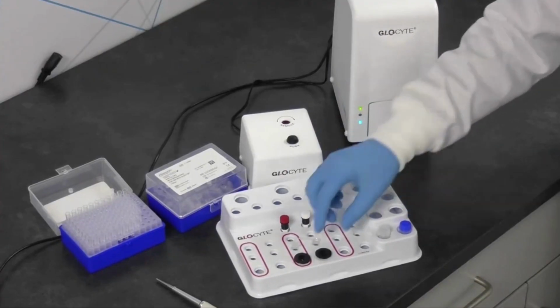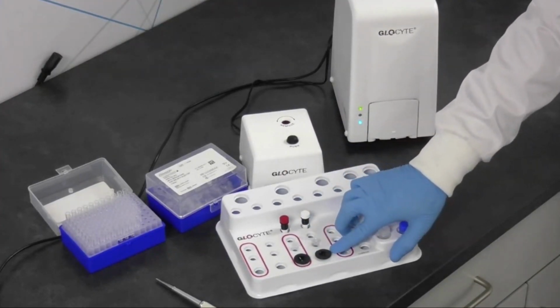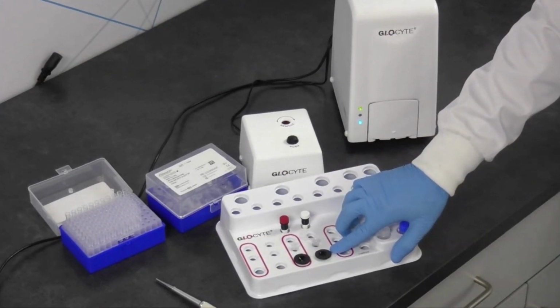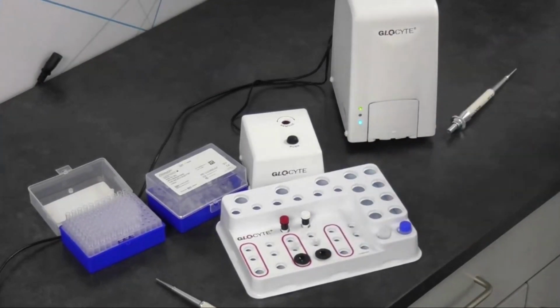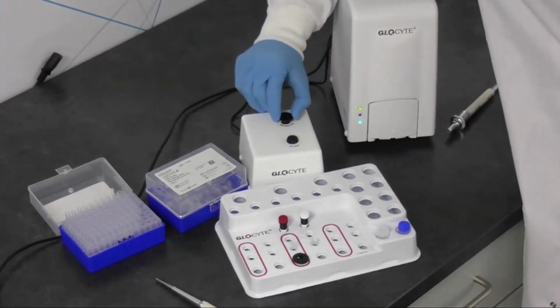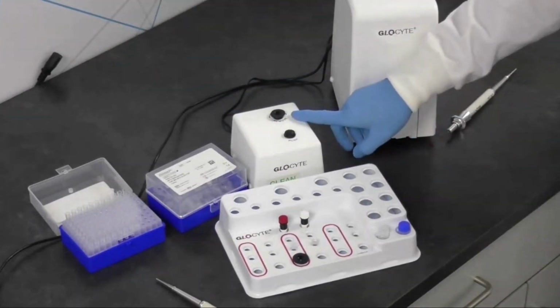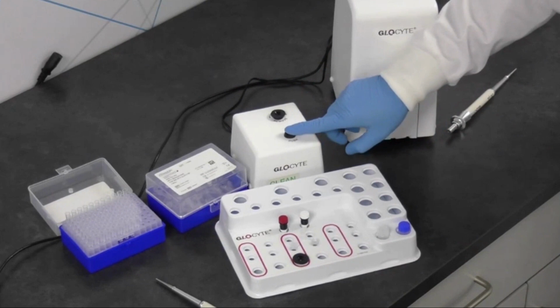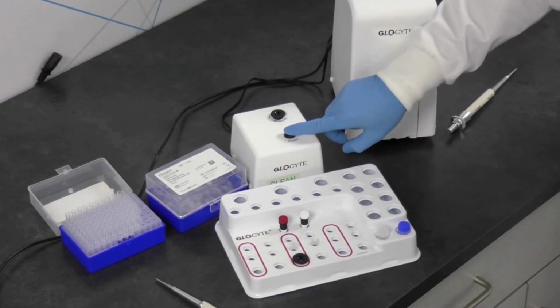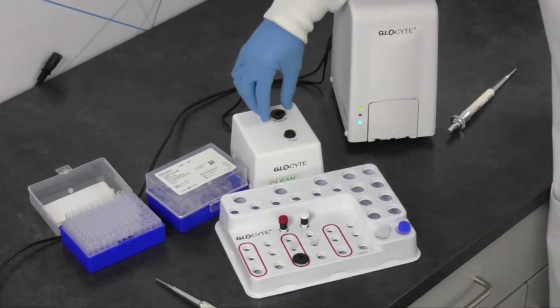But before we put it on the GloCyte instrument, first we need to take the fluid that I just put onto the membrane and suck it down into the cartridge so we can actually trap those cells on the membrane and get a good image with our GloCyte analyzer. So this neat little gizmo here is our vacuum chamber. You simply load it here and you hit push. And it sucks that CSF sample down into the bottom of that cartridge.